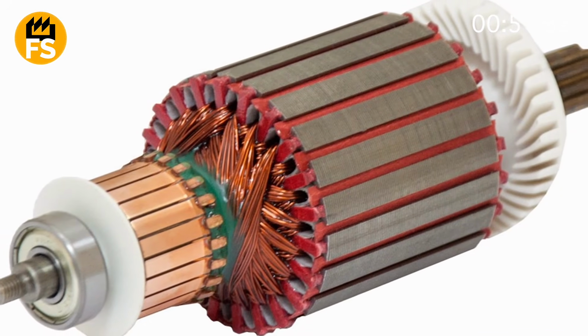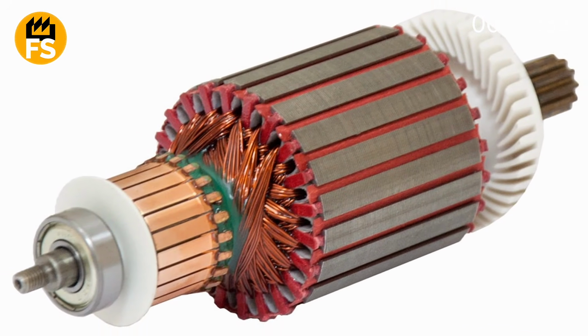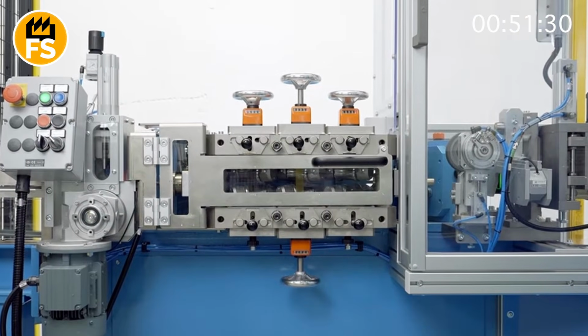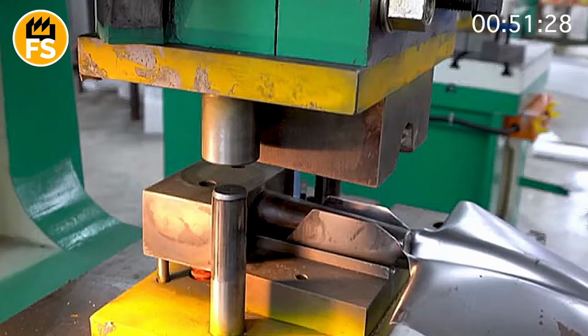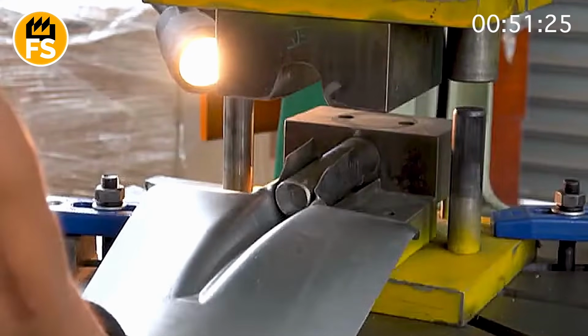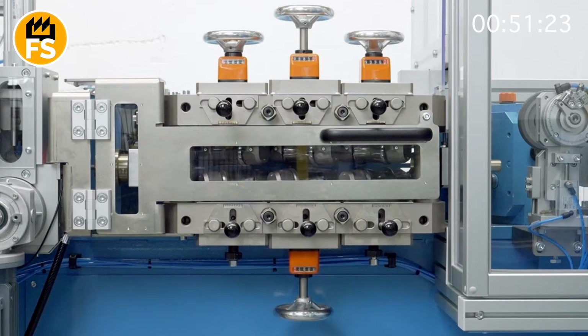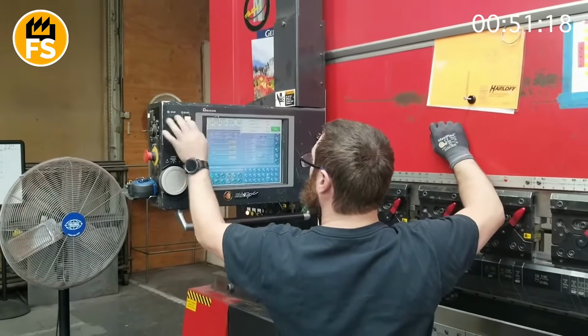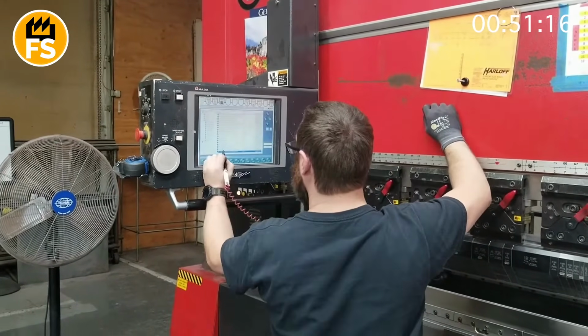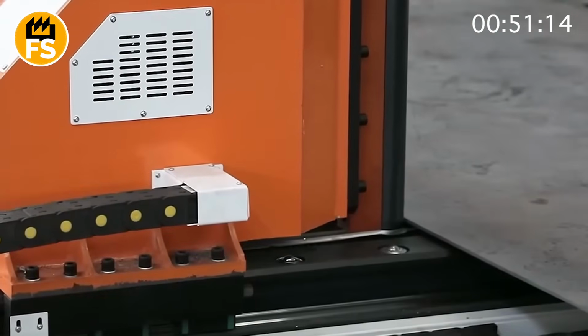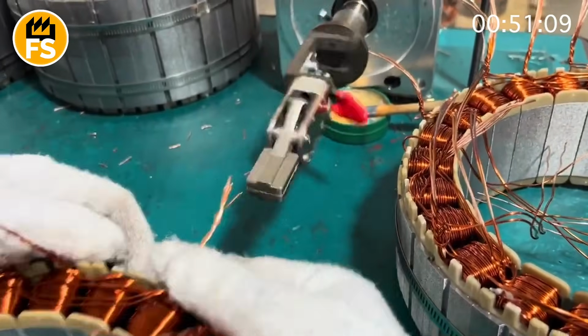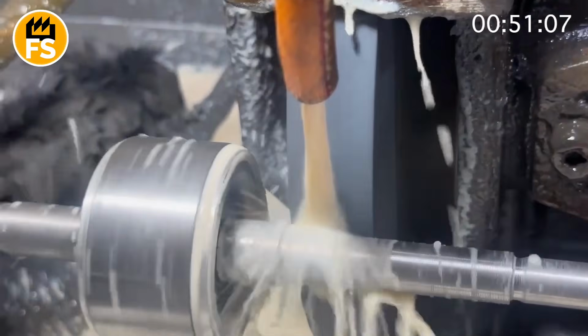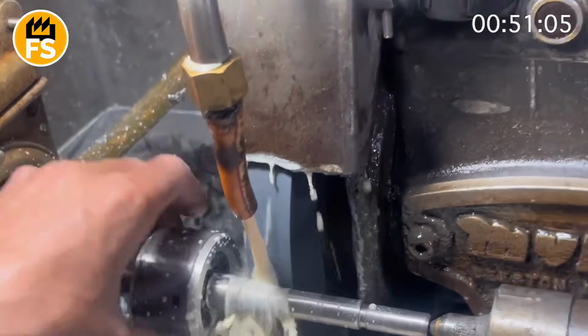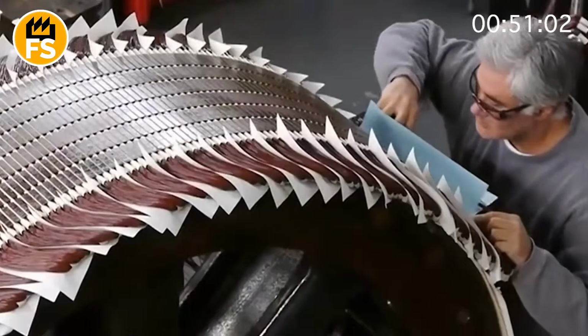The rotor is mounted inside the stator via bearing assemblies. Sometimes special guides or hydraulic presses are used for this. The rotor shaft must rotate perfectly straight, otherwise everything will vibrate or break down within a week. At the ends of the rotor shaft, sleeve or rolling bearings are installed. They allow the rotor to rotate without friction. The bearings are placed in so-called end shields, which are then attached to the motor housing. All surfaces are pre-lubricated with special greases to ensure durability.